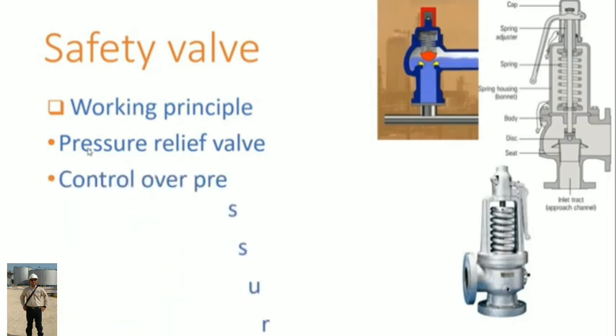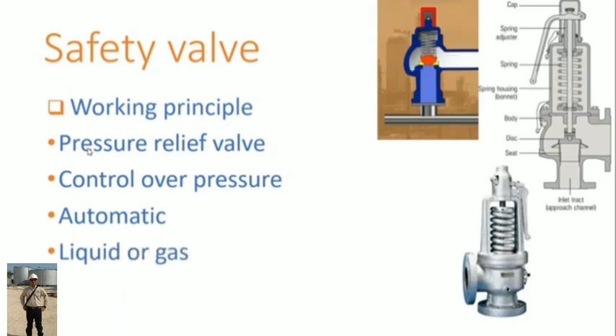Working principle of safety valve. Allowable pressure is balanced by a spring, and over-pressure conditions in the system are controlled by releasing the flowing fluid to the out of the system as shown here. Also known as pressure relief valve. When the pressure increases, it works automatically to ensure safety. They can be used for both liquid and gases and are commonly seen in steam lines.